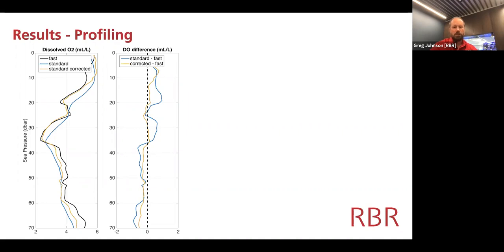But it does go to show that effectively you're able to deconvolve the slow behavior. And as long as that drop rate is constant, you'll be able to get improved results this way if you're interested in doing that. The advantage of the standard over the fast is that much lower drift characteristic. So if you're in a situation where you're profiling, but repeatedly over a long period of time, for instance, on a wire walker or an Argo float, then using the standard thermistor with its lower drift is a much better approach.